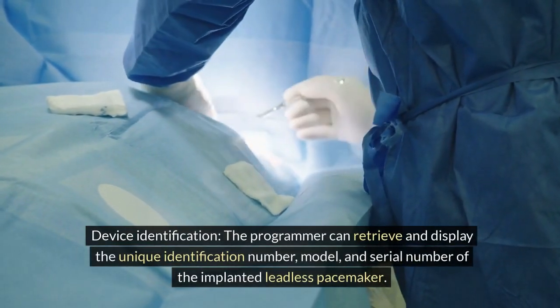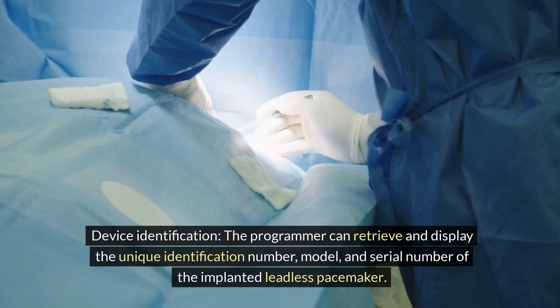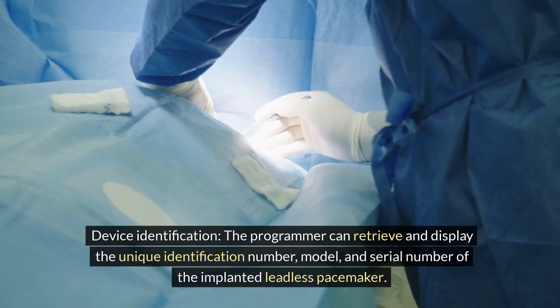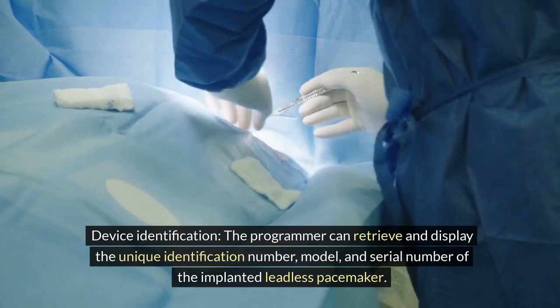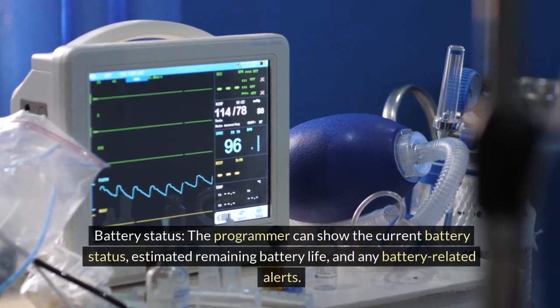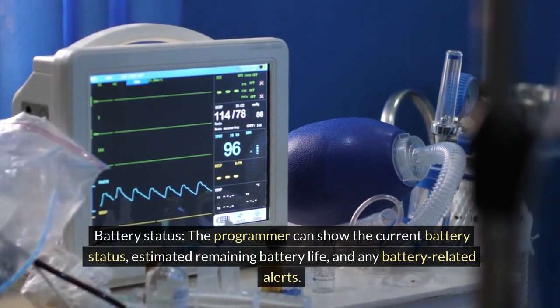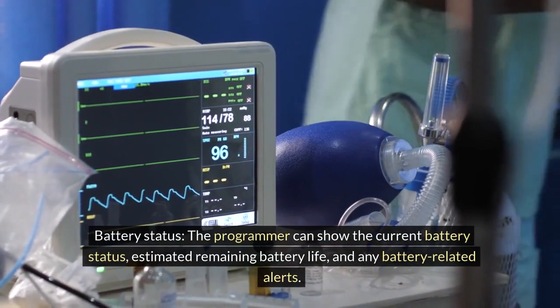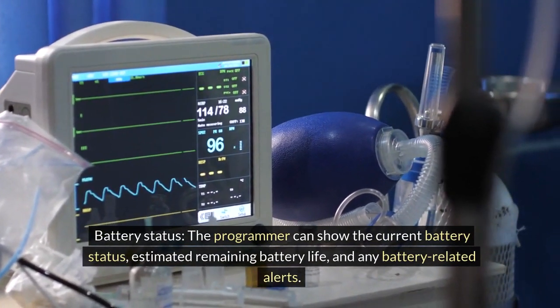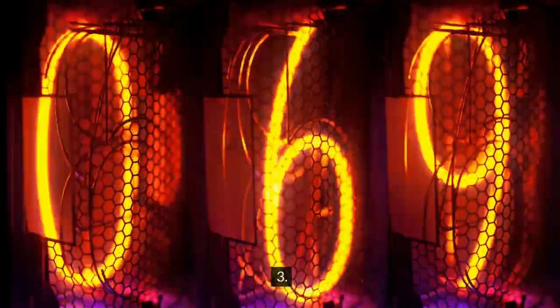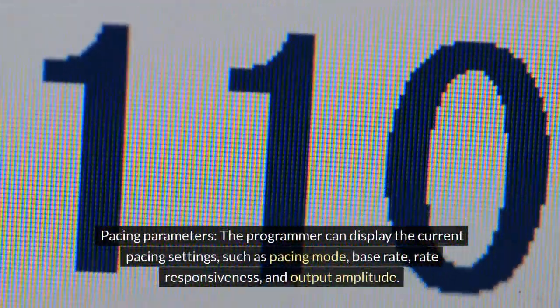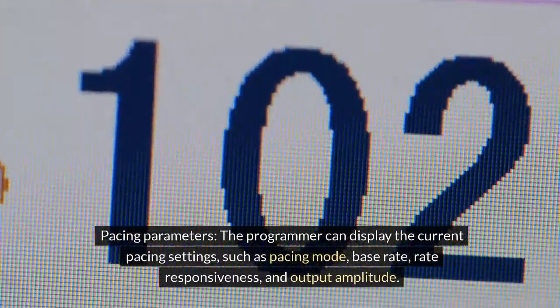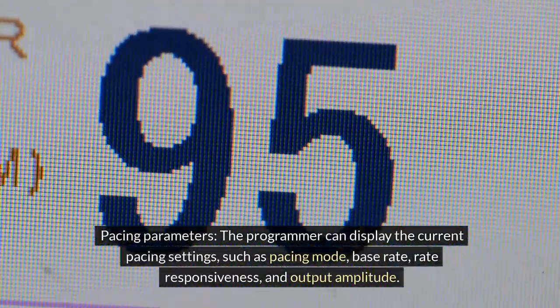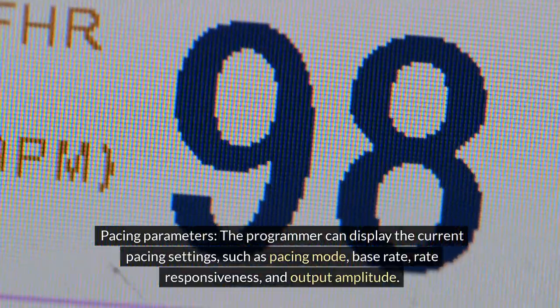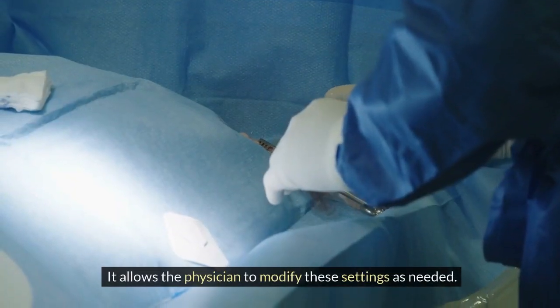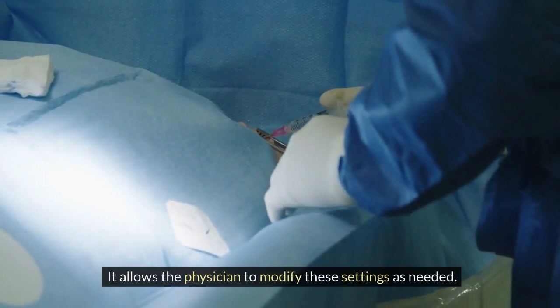The programmer can retrieve and display the unique identification number, model, and serial number of the implanted leadless pacemaker. 2. Battery status. The programmer can show the current battery status, estimated remaining battery life, and any battery-related alerts. 3. Pacing parameters. The programmer can display the current pacing settings, such as pacing mode, base rate, rate responsiveness, and output amplitude. It allows the physician to modify these settings as needed.